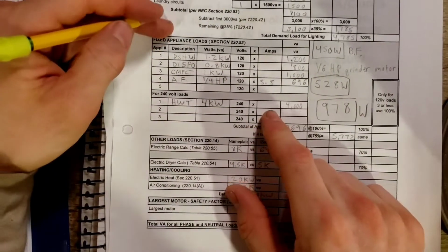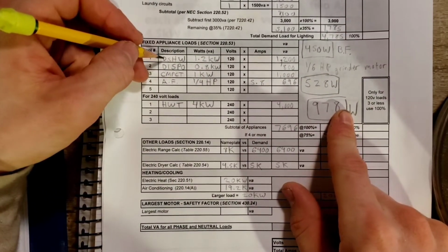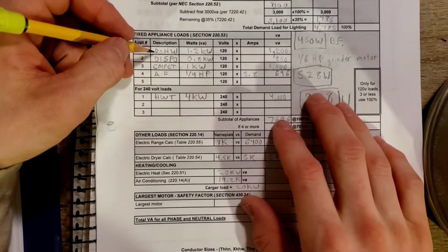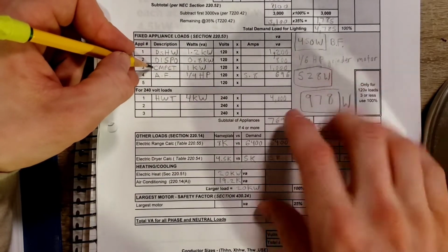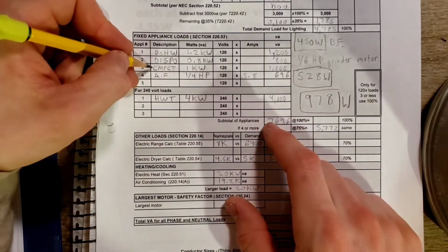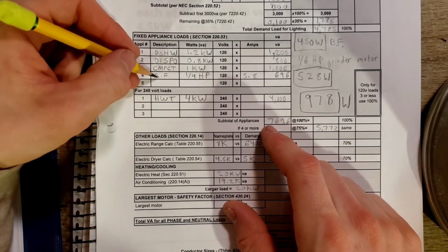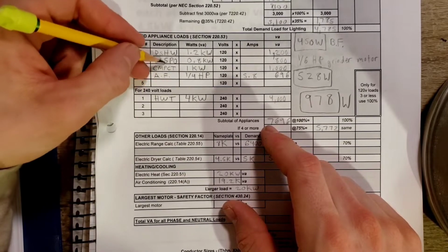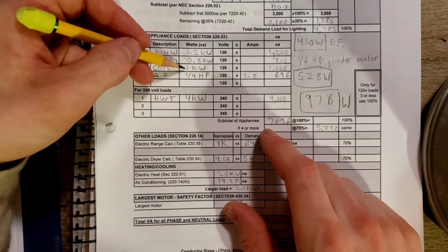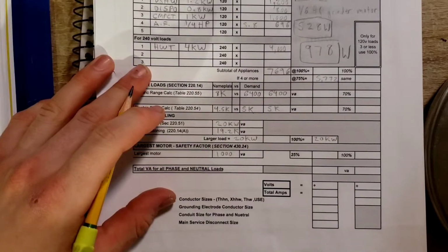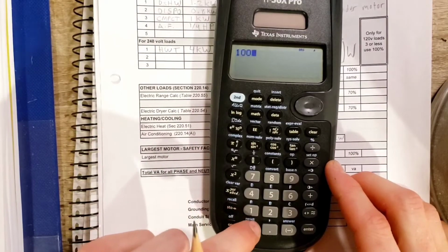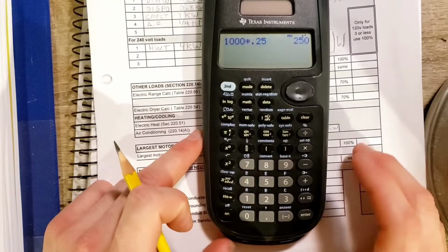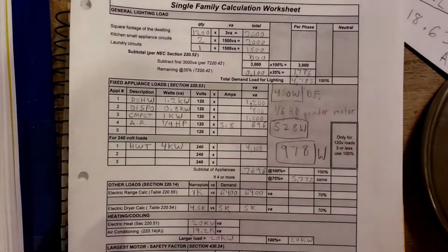So let's think, what here has a motor? What doesn't have a motor? Okay, you have a dishwasher. That might not have very much of a motor. You have a disposal. Okay, that's a definite motor. We could all think about that. We have a compactor that most likely is going to use a motor. And then we have our attic fan. So out of these 3, which is your highest, we got our compactor, which is 1 kilowatt or 1,000 watts. So we're just going to get our 1,000 watts. We're going to times it by our 0.25. So we're going to get 250 watts.